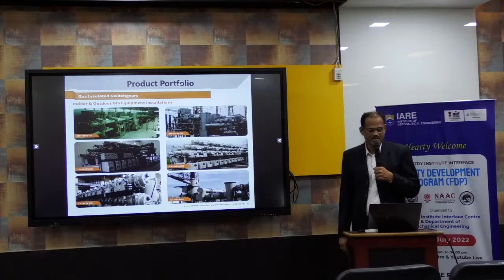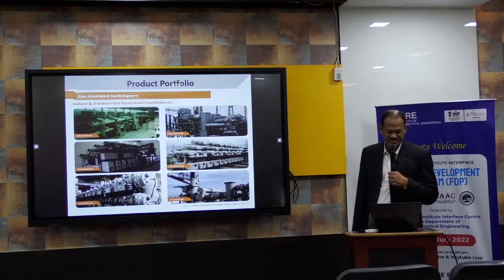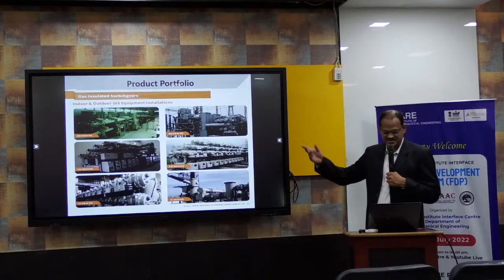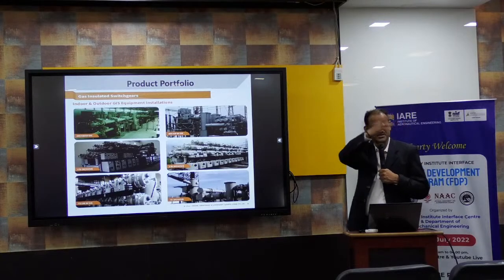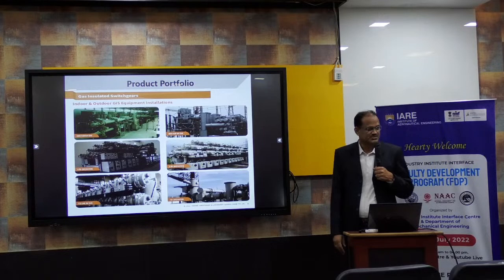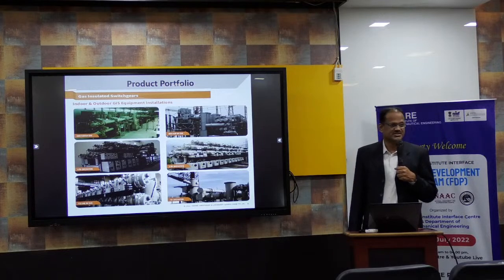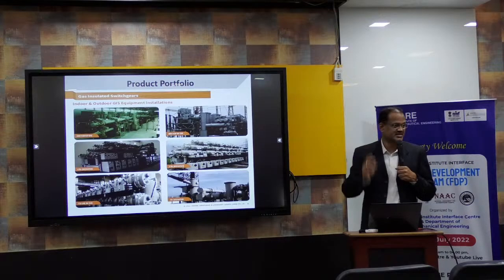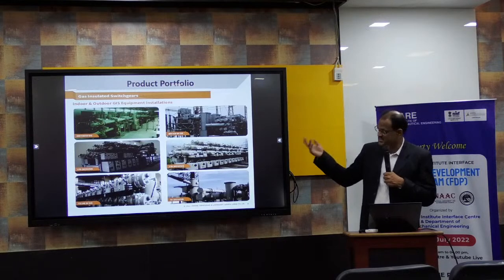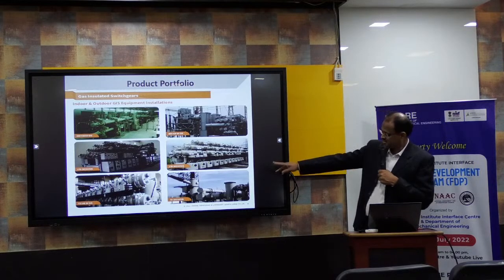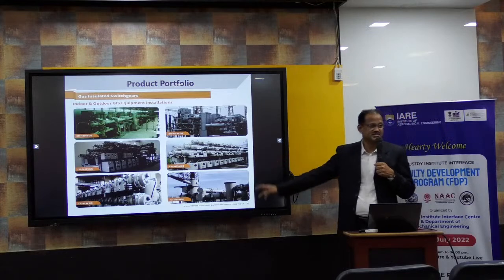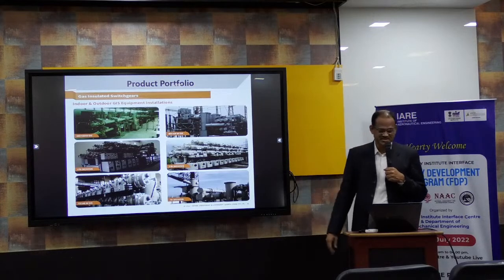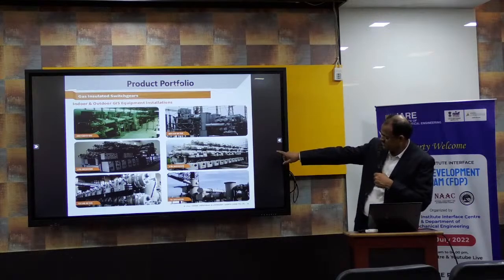Next portfolio, gas insulated switchgear, indoor and outdoor GIS equipment installations. Normally you can see substations everywhere. Substation means air insulated substation. You can see bare bushings, bare conductors, everything. Whereas in this technology, all controls, circuit breakers, everything is built into the tube and the control circuit only.